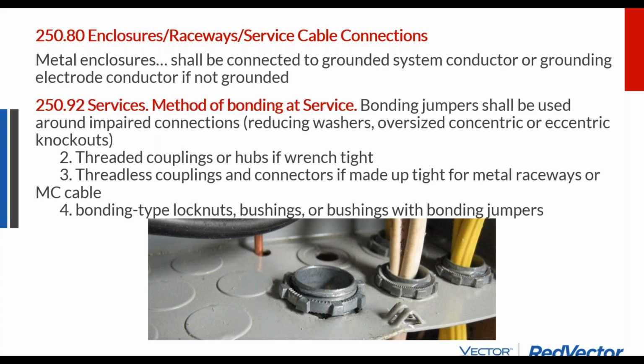For the ground path between metal conduit and your electrical box, you get these rings that are called concentric, where there's an internal knockout and an external knockout. It's only considered grounded if you use the external knockout. If you use the internal knockout, it's an impaired connection. And so you have to use an additional ground wire that comes off of the connection and carries through the rest of the system if you're using those impaired connection holes.